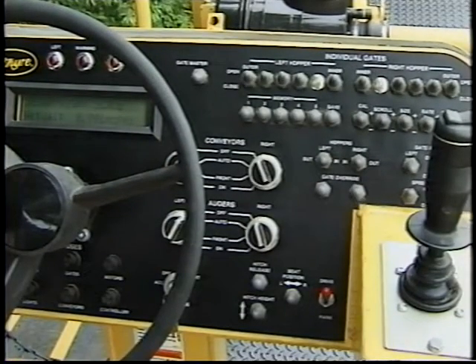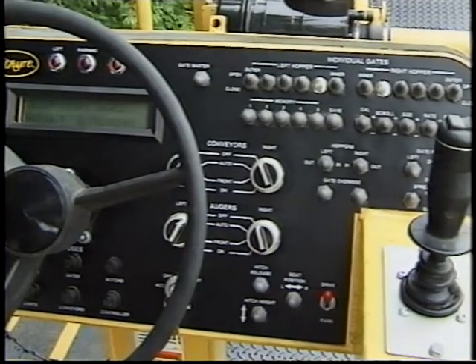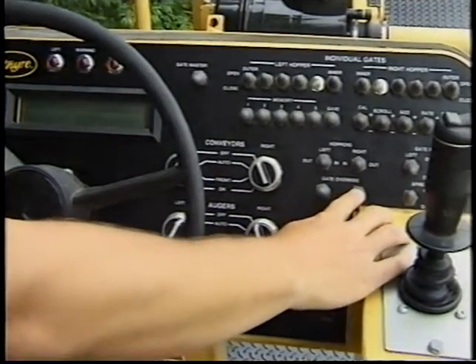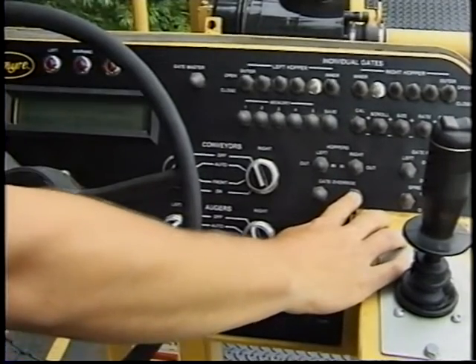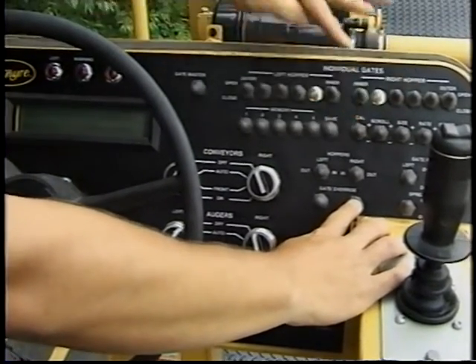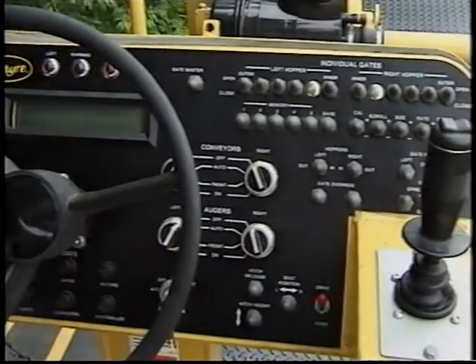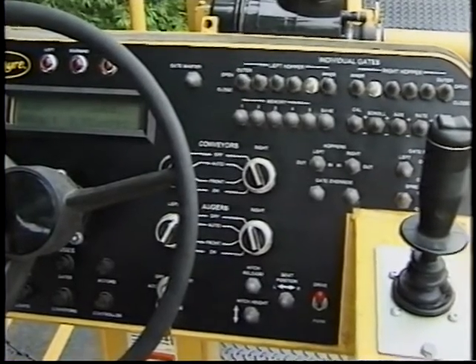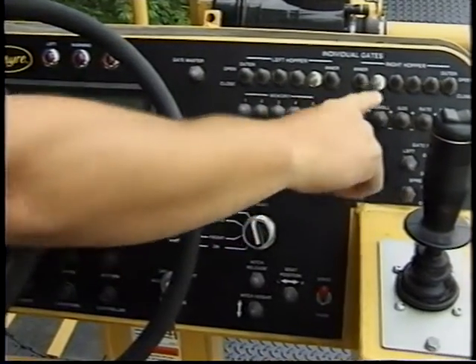This screen is used to set the full open position of the right gate. Press the right gate override button, and while holding the override button down, press the CAL switch. When the open position has been set, push the scroll switch down to move to the next screen.